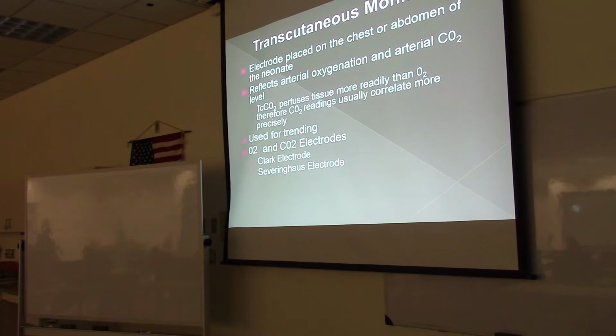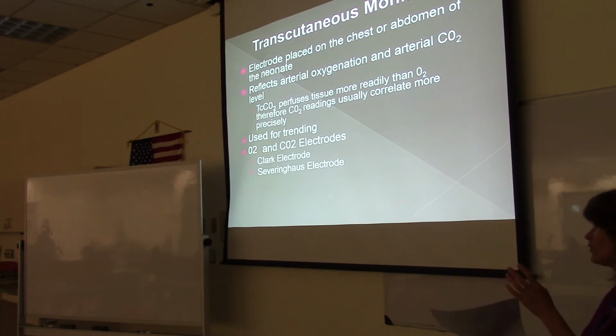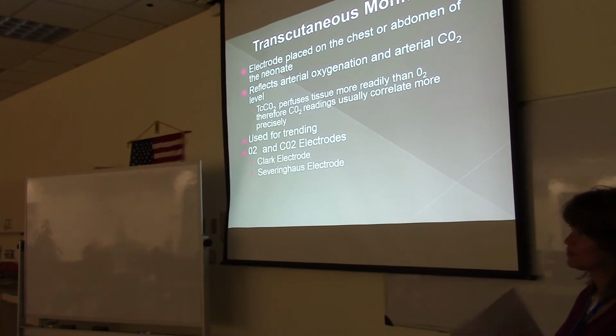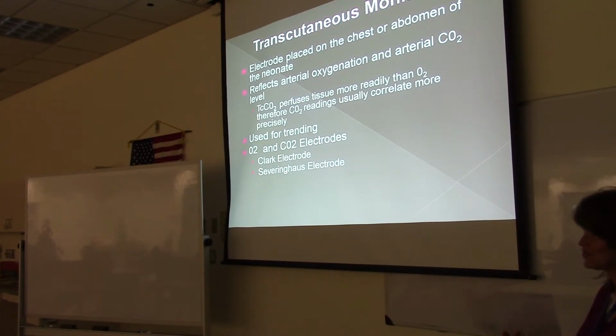So you could have a transcutaneous monitor measuring carbon dioxide and get a number, and then draw arterial blood, and they'll be very similar to each other. Oxygen, not so much. There's about a 10-to-1 difference between what the transcutaneous oxygen level is and when you're actually drawing arterial blood. All right, so it says electrode is placed on the chest or abdomen of the neonate. It reflects arterial oxygenation and arterial carbon dioxide. TcCO2, transcutaneous carbon dioxide, perfuses tissue more readily than oxygen. Therefore, carbon dioxide readings usually correlate more precisely. The numbers are used for trending.